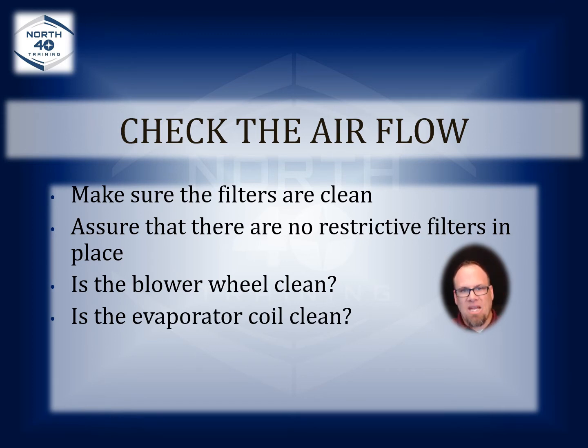We don't have as many evaporator issues now as what we used to because we have a secondary heat exchanger now that rests just above that blower. And so oftentimes the secondary heat exchanger is going to catch all of the junk that used to get caught in the evaporator coil. However, anything that gets past there that's a much smaller particulate like dust and pet dander and things of that nature are going to catch on a nice wet coil. So the evaporator coil can still get dirty, and especially if you're using filters that are the least amount of restriction, which are those fiberglass filters.